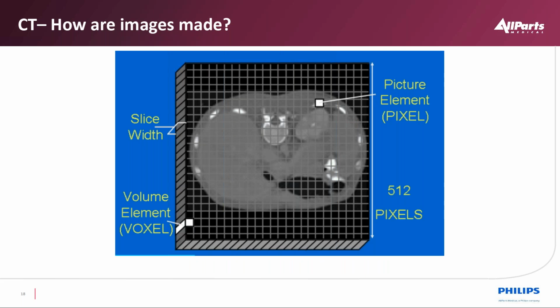So when we scan a patient, we not only have X and Y, which you see here as far as a grid, we also have the depth that represents. And if it was a 5 millimeter slice or a 1 millimeter slice, that would be the average of those CT numbers in that depth. So as we approach what we would call isotropic imaging, the depth of the slice would be the same as X and Y. Okay, so this is showing a grid of 512 by 512. And with that, the newer scanners represent a 1024 by 1024 matrix, which basically is 4 times the data set. So what you're looking at is a CT number being in each one of those voxels, and that being represented in a grayscale.